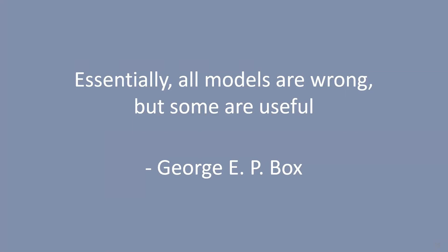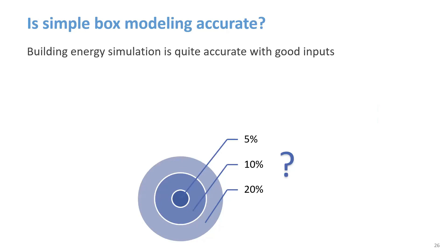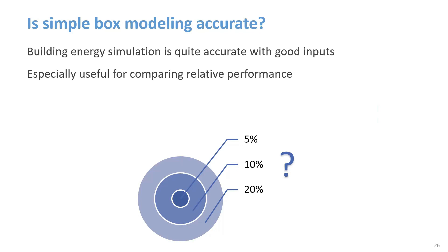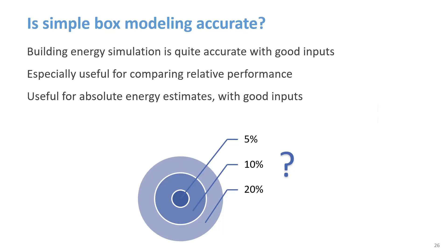How about some questions about simple box modeling — is it accurate? Building energy simulation programs are quite accurate when we provide accurate inputs, and that's clearly a challenge when creating a simple box model at a very early stage when many assumptions are necessary. It's especially useful for comparing alternatives, since relative performance is less sensitive to those assumptions compared to an estimate of absolute energy consumption. It can also be useful for absolute energy consumption estimation with good inputs.